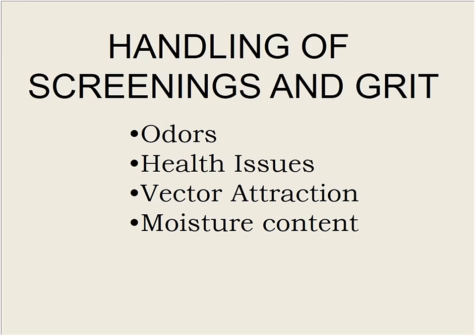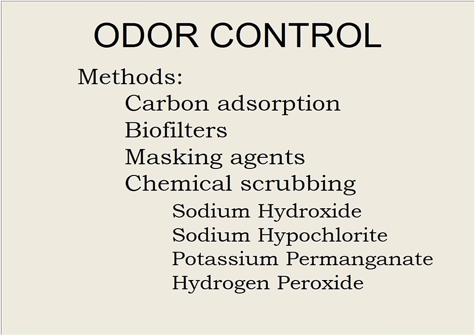Again, wash the organics off our stuff before we get rid of it so it can go to the landfill, and they can't get after us. And the moisture content. Go to a landfill, you typically have to have greater than 20% solids of whatever it is you're sending. So we have to try to make sure that it's dry enough to be able to go without any problem. Again, odor control, these buildings tend to fall under an odor control situation as time goes on.